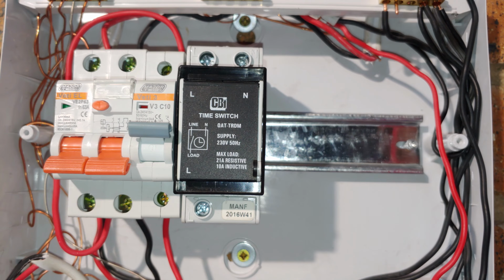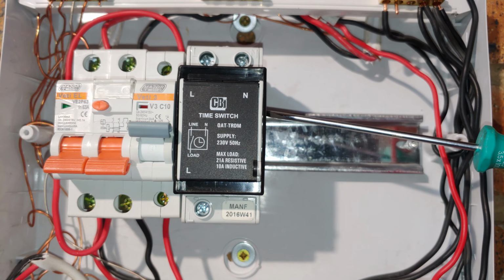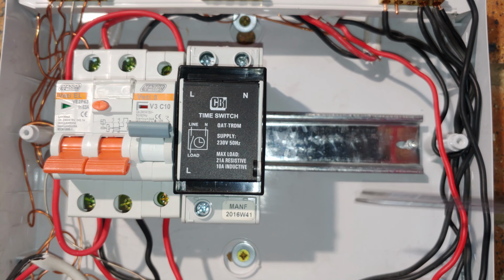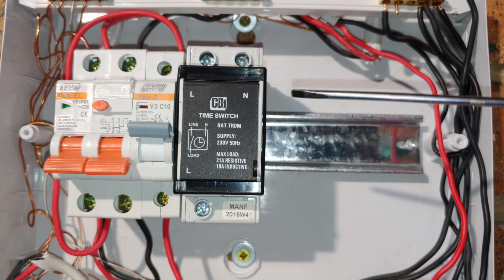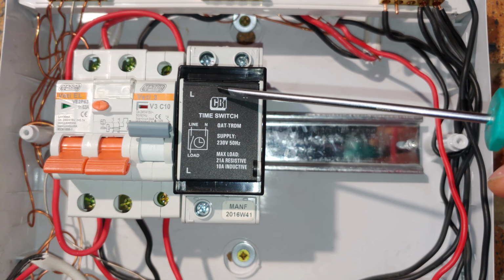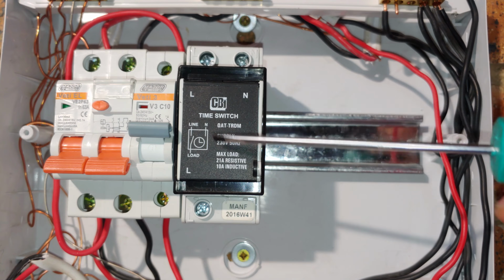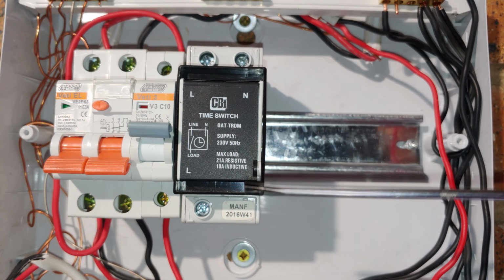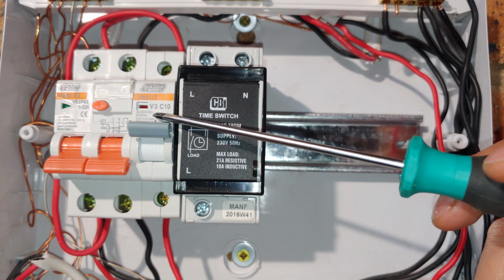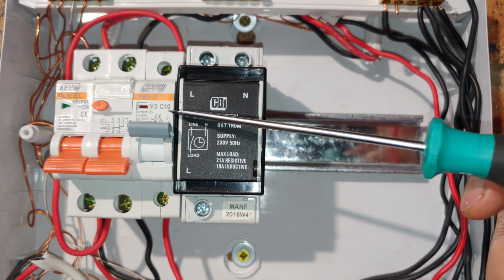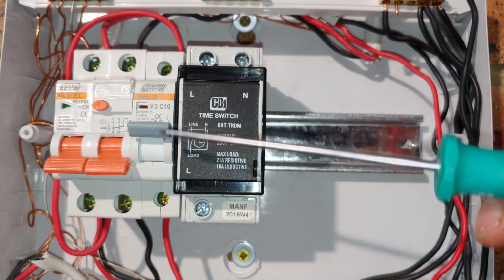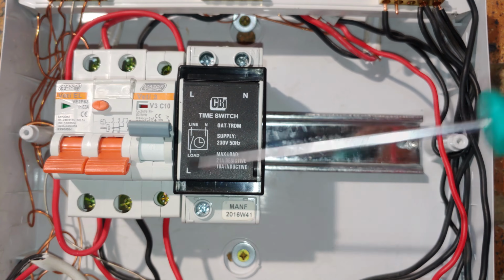That means that if there's a fault on the motor, the timer switch offers no protection function, meaning it will not disconnect the load. All it will do is look at its timing sequence and switch it on and off according to the program. While the circuit breaker, if there's a current that is above, in this case 10 amps, wanting to flow here, the circuit breaker will trip.